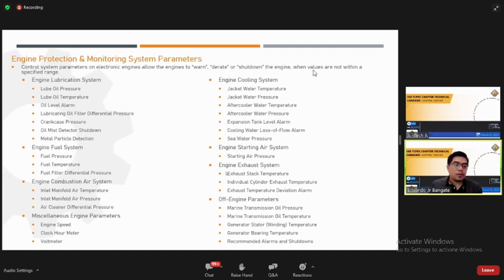What about the fuel engine system? Fuel pressure, fuel temperature, fuel filter differential pressure. Again, the differential pressure to determine if your filters are blocked. Engine combustion air system, what do we monitor? Inlet manifold air temperature, inlet manifold air pressure, air cleaner differential pressure. Napaka-importante. Engine cooling system: jacket water temperature, jacket water pressure, after cooler water temperature, after cooler water pressure, expansion tank level alarm, cooling water, seawater pressure, kung seawater ang ginagamit natin sa cooling. Okay. Engine starting air system, again, for those black start na kailangan ng air compressor. Engine exhaust system: exhaust stack temperature, individual cylinder exhaust temperature, and the exhaust temperature deviation alarm.